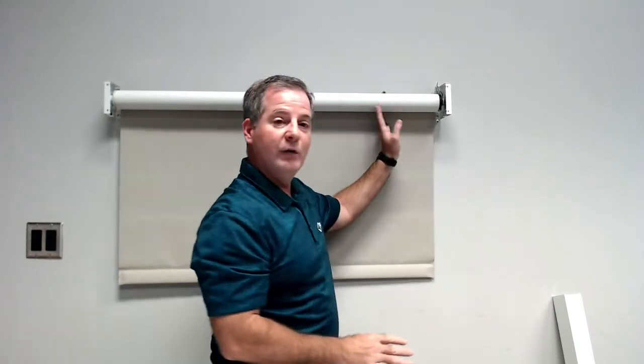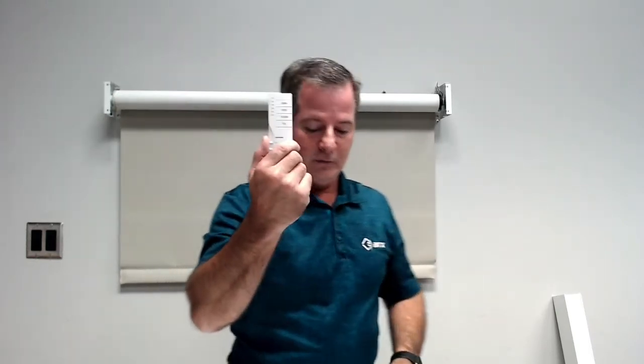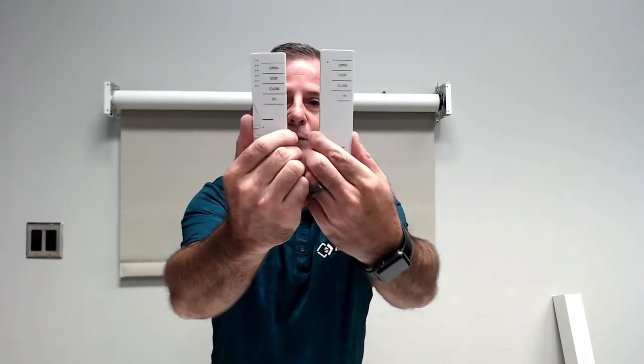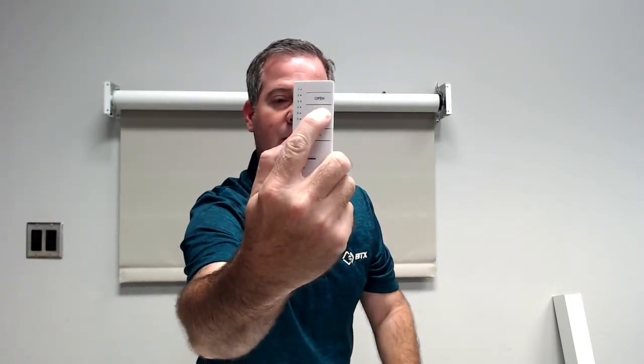Before you pair this particular unit, you must put this particular motor into a pairing mode, and that needs to be done with the original six channel or one channel remote. So here we go, since this was working on channel one, you're going to hold the stop button down with a fast flash until the motor jogs.